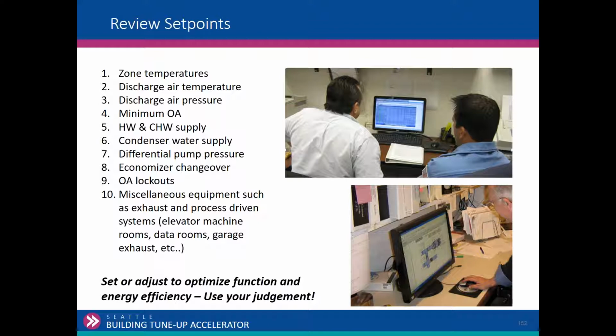Hot water and chilled water supply temperatures, do they make sense? It's 30 degrees this morning, so I'd expect my boiler water to be 180. When it's 50 degrees outside, it should be 160. So what are we using for water temperatures? Does that make sense? Condenser water temperatures.